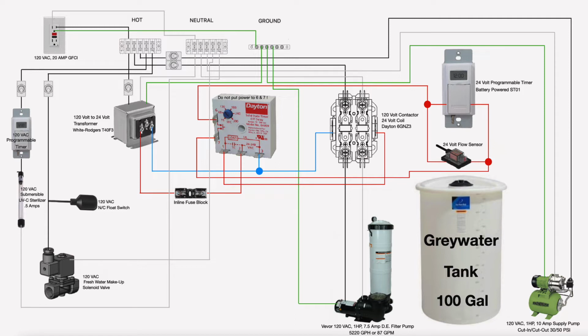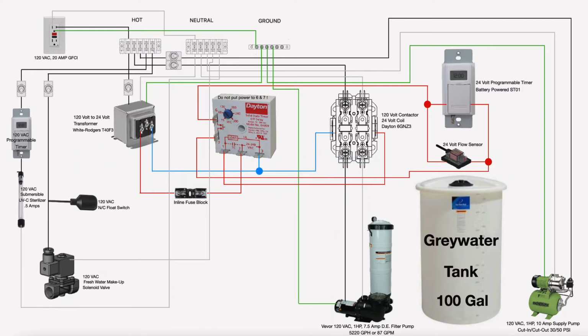As I said at the top of the video, this is about the wiring schematic, or how to wire your gray water reclamation system. So as you see here, we got 120 volt single phase AC power coming in to our control panel on the top left corner here. This is a 20 amp GFCI. You could also use a 20 amp GFCI circuit breaker. The way you determine what size circuit breaker or what size outlet you need to use to supply your gray water system, you need to add up the ampacity of your filter pump, your supply pump, and your UVC sterilizer. In this case, we're right at about 18 amps, so we're pretty much maxing out that 20 amp dedicated circuit for this gray water system.